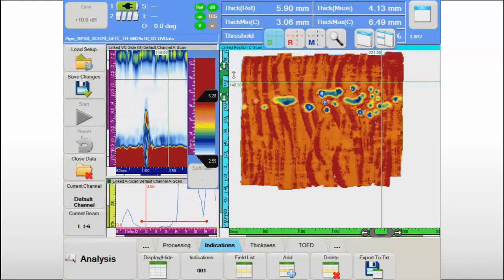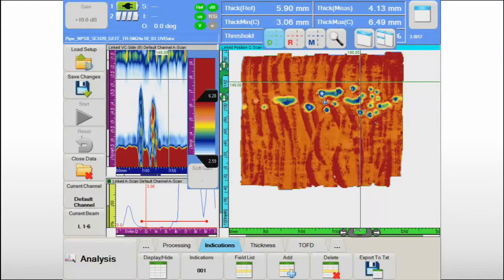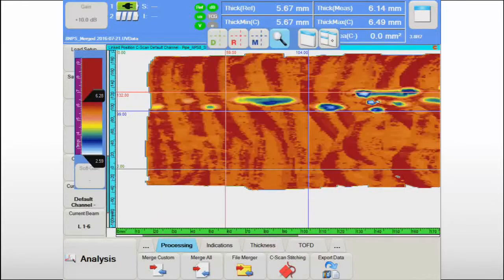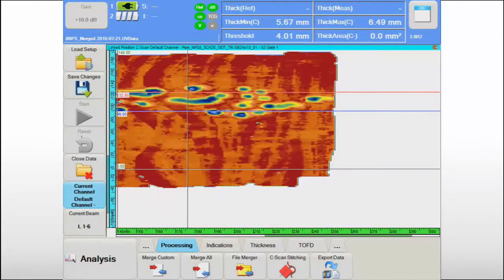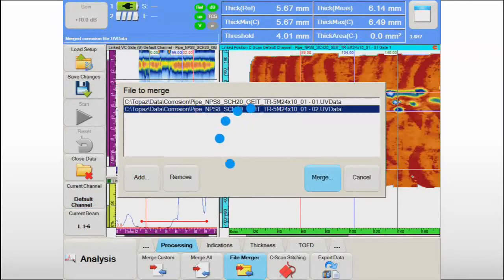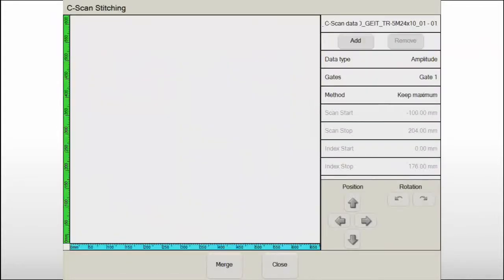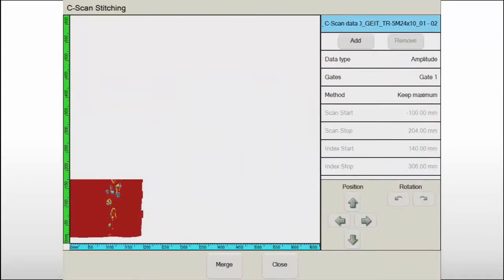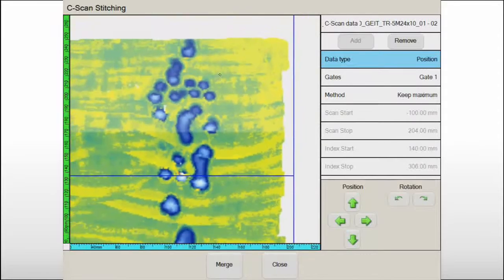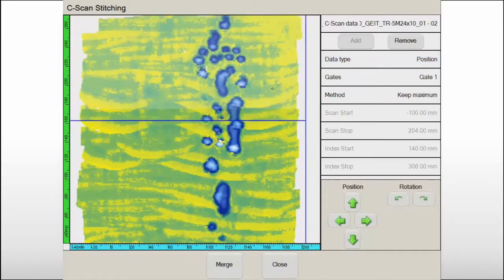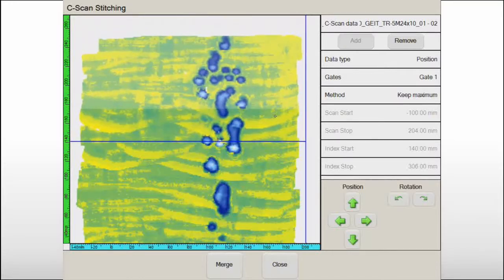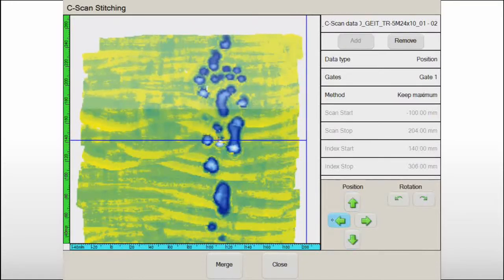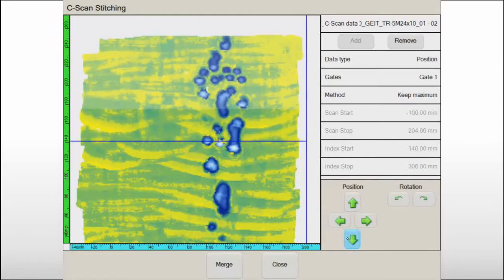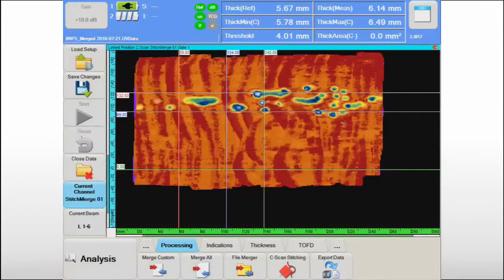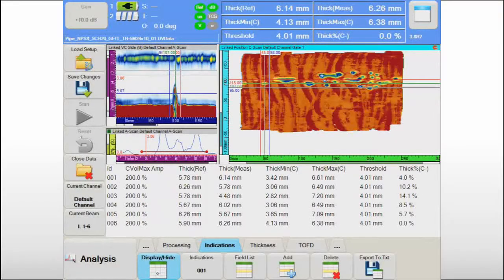On flat surfaces or large cylinders, the typical region that will be covered in a single scanning sequence is roughly 2.5 feet by 2.5 feet. Many times, the region of interest is larger than that. Therefore, it may be necessary to merge data together to give the data analyst a global view on the status of the component and for final reporting. The C-scan stitching feature in UltraVision Touch helps the operator accomplish this through an efficient and simple user interface. After merging the data files, C-scans are stitched together with the ability to compensate for typical small misalignments and misorientations between datasets. The global C-scan image is then saved and ready to be used for further investigation.